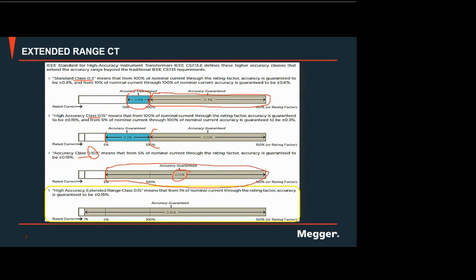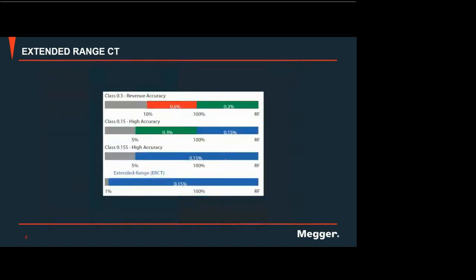Now here, extended range CTs of 0.15, for example. Look at this graph here. The 0.15% can go down up to 1% of the rated current, meaning the extended range CT is accurate up to 1% of the rated current. Even if the load is 1% of the rated current, you can obtain 0.15% error. There's a better view here. Extended range can go down to 1%.